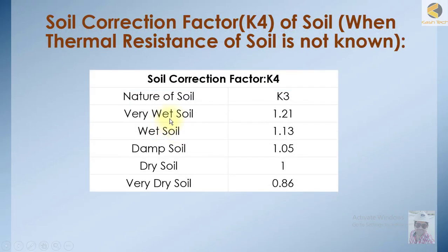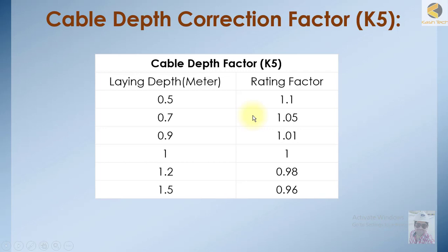Then we have the soil correction factor. If the soil is very good, the correction factor is favorable because the soil will conduct heat properly and the conductor can be used at higher currents. For example, this could be the case near the sea where the soil is very wet. Then we have wet soil, damp soil, dry soil, and very dry soil. As the soil gets drier, the K factor goes down.